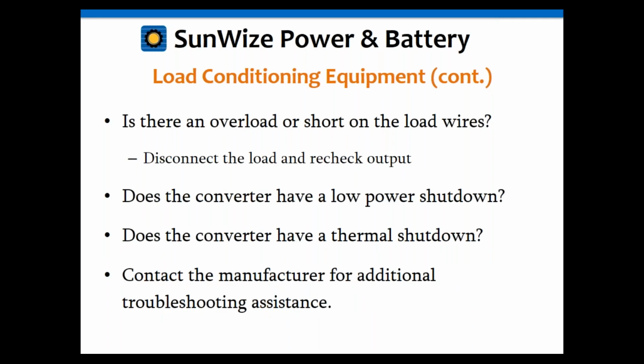Okay, another common one is a short circuit or an overload on the load wires. Just like you can find on the solar array, there could be an overload or a short somewhere. Maybe two wires got caught together, who knows? Generally, most of the converters or inverters have an overload protection that shuts down in an overload or short circuit situation, so you might want to check for that.